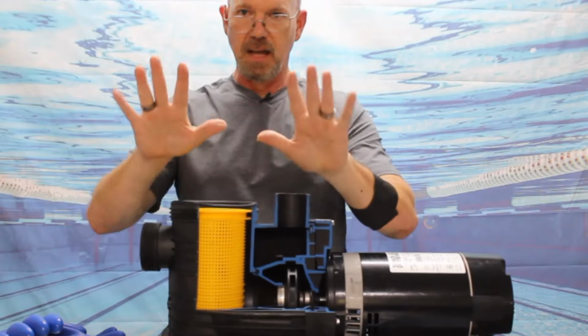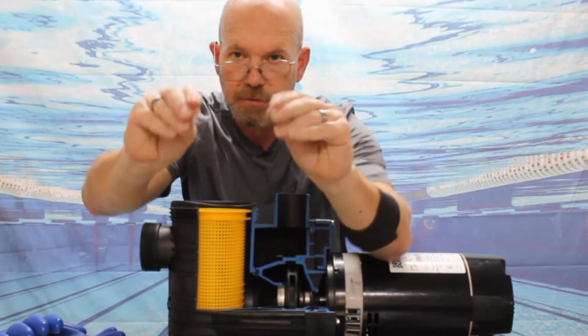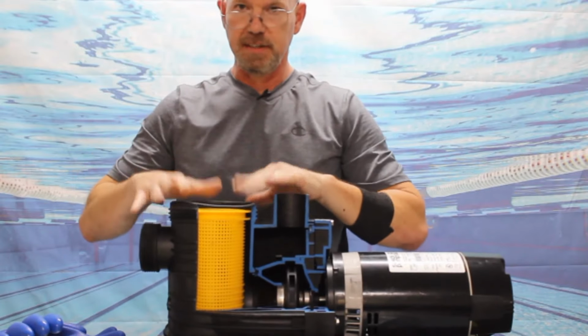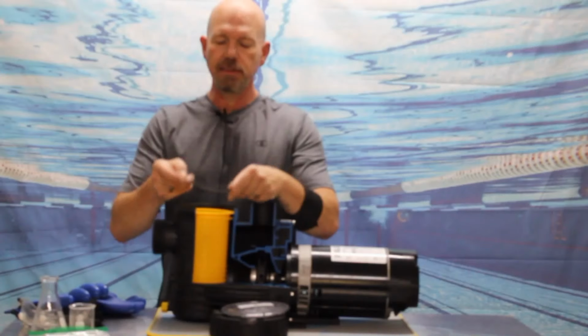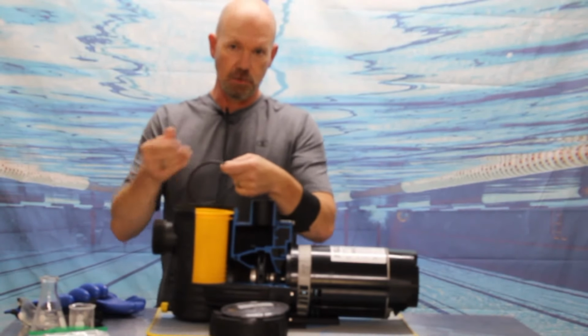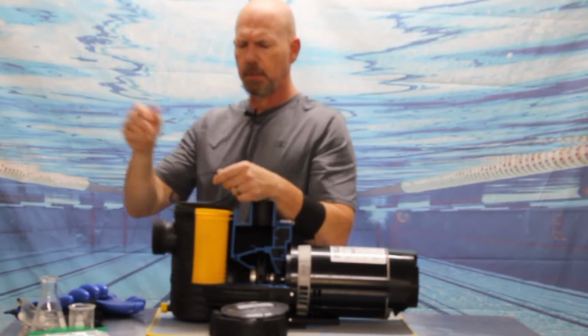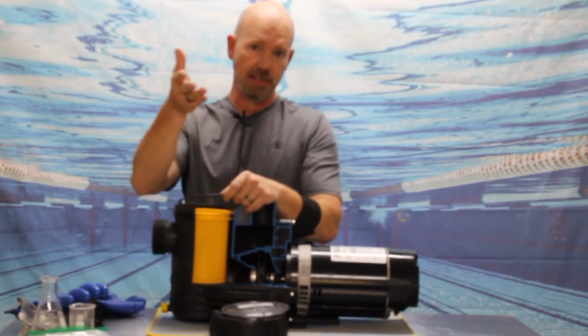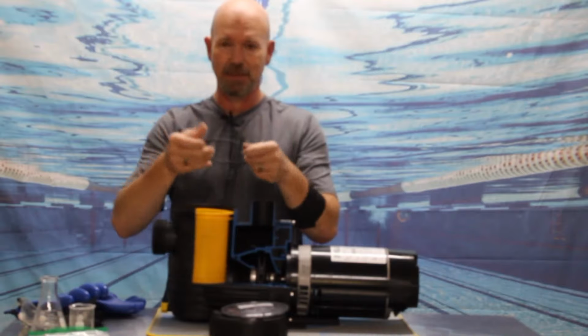Before we put the lid on, take a look at your fingertips. If your fingertips have turned black from handling that O-ring, you'll want to replace it. It means that it's starting to degrade. This is another common place where you can see a fail and draw in air. Sometimes when you shut the pump off, if this O-ring has failed, you'll see it spit a little bit of water out. That's also an indication that this gasket needs to be replaced.